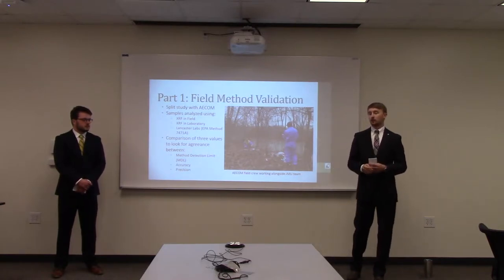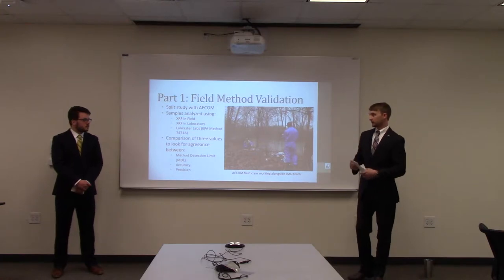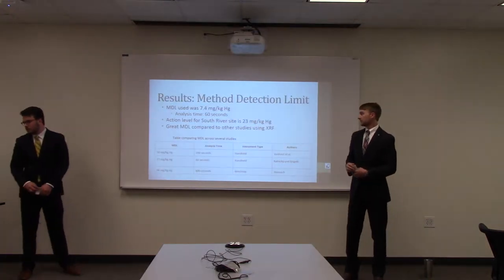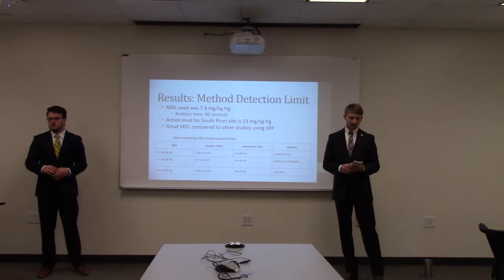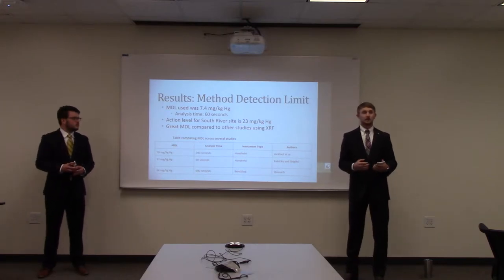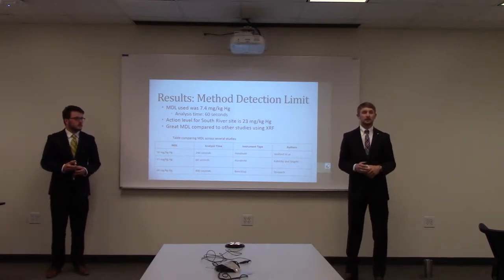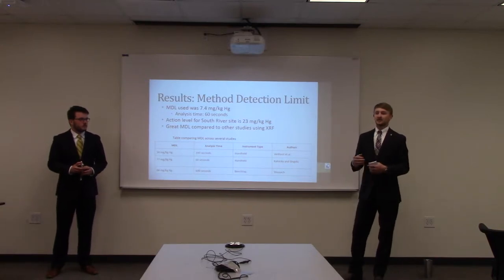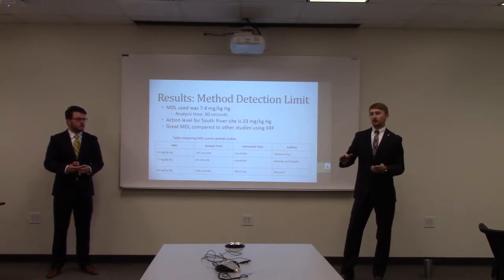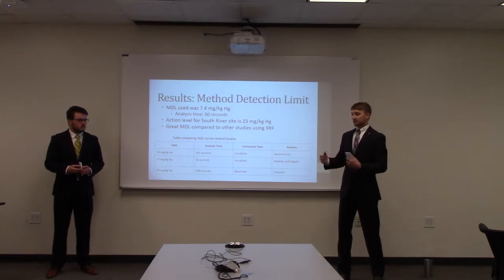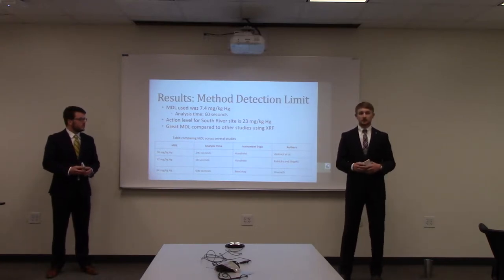what the sensitivity on our device is. How low are we able to detect mercury in these soil samples? So the first thing we looked at was the method detection limit. What we were aiming to do here is verify the method detection limit that Nathan had created. The method detection limit is simply how low our device can read the mercury, so it's a measurement of sensitivity on how well our device was going to work.